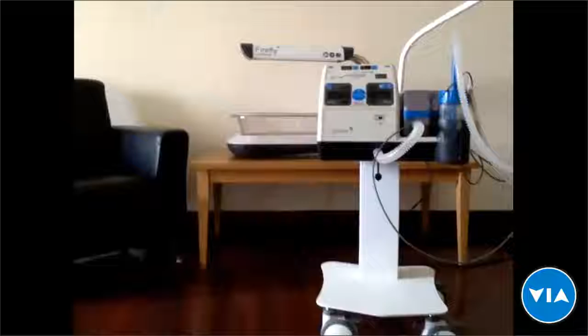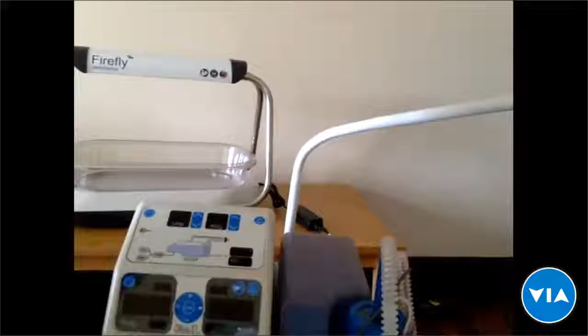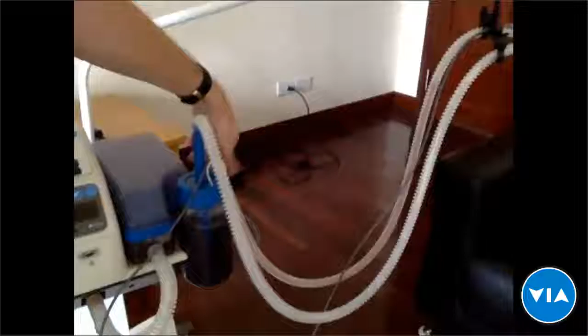Bubble CPAP device, which means that we have a PEEP bottle that generates the pressure, the humidifier that is humidifying the air, and this humidified pressurized air is delivered through the heated patient circuit to the patient. We control the oxygen level as well and the flow. So we have 5 controls that are allowed for the user, and these are exactly the same controls that will be used in the developed world.